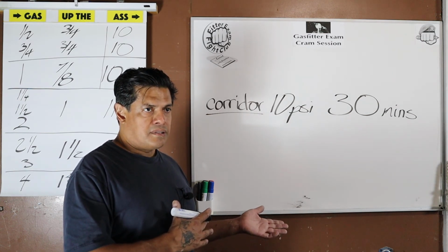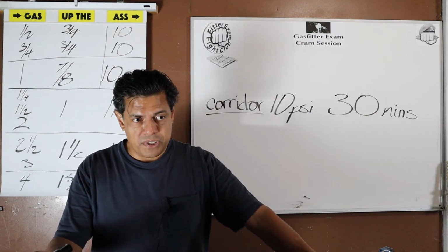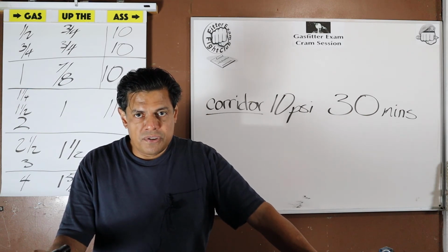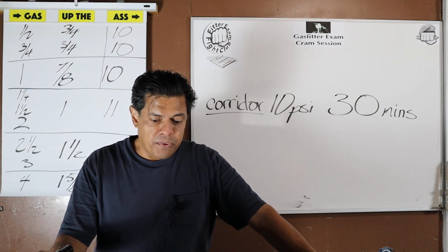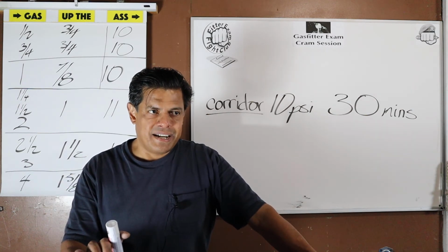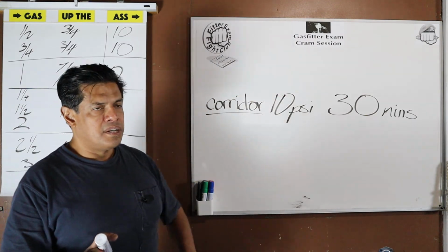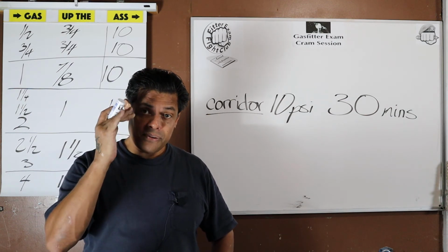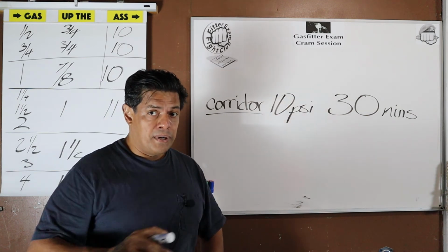Okay, unless you want to, I guess you could also say, well, since the code says the distribution system is going to be tested in its entirety, because it does say that. When we get into testing, that's another stipulation. They want to test it in its entirety. An argument could be made, well, you got to test the system all at once, and even though you only need to test a half PSI system at 3 for 30, you have a section that requires 10 for 30.